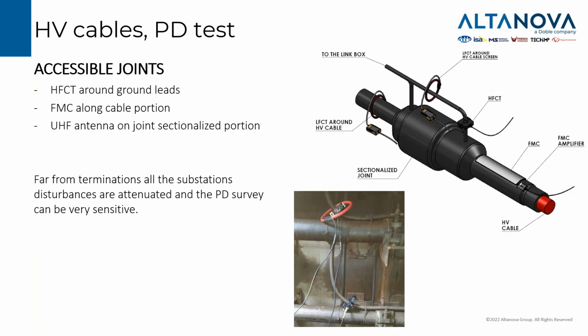In case we have tunnels or manholes with accessible joints, and the joints are armored, so we are in a safe condition to enter the place, we can use HFCT on the single bonding cable, single core bonding portion of the concentric cable that goes to the link box, or we can use the flexible magnetic coupler over the joint and over the cable.